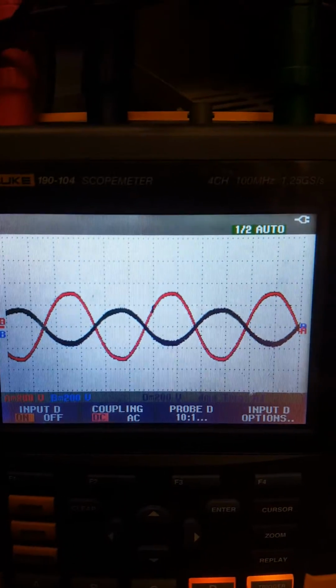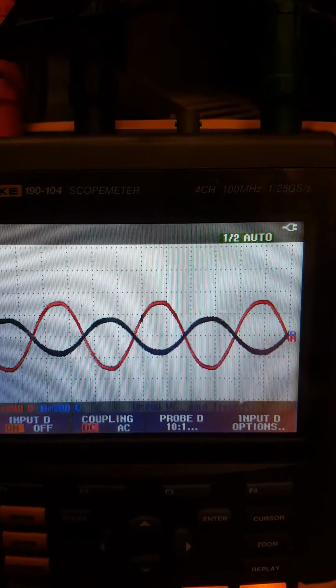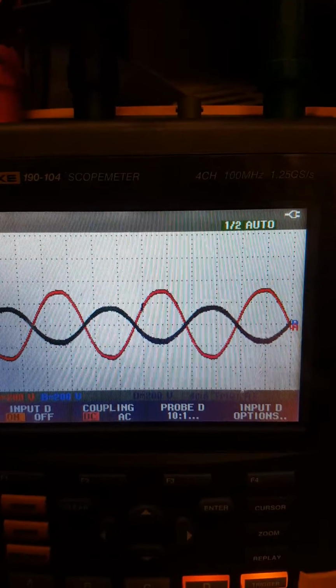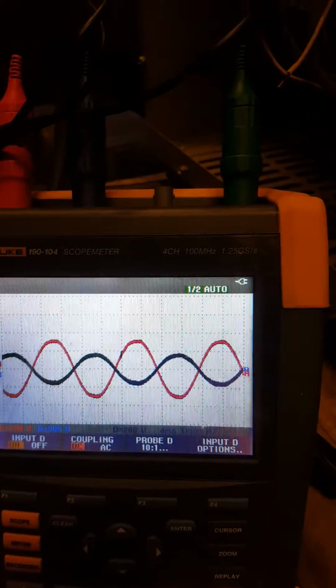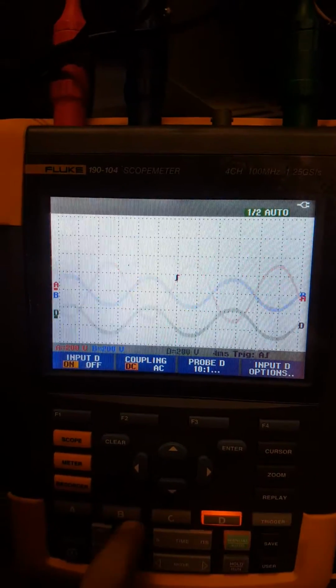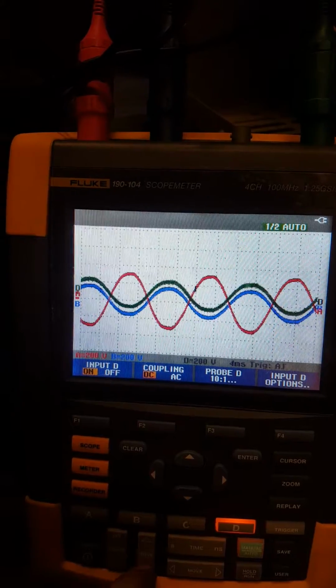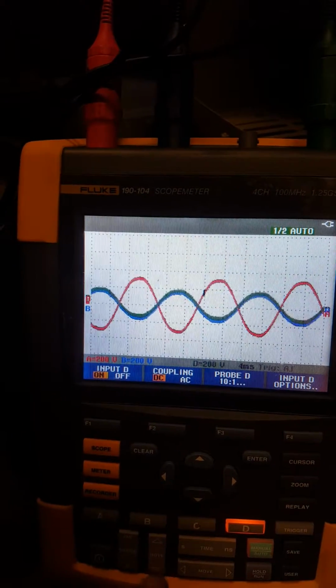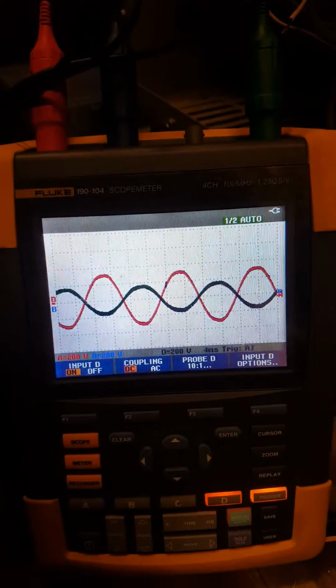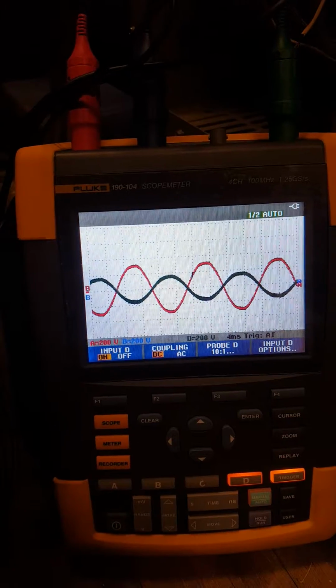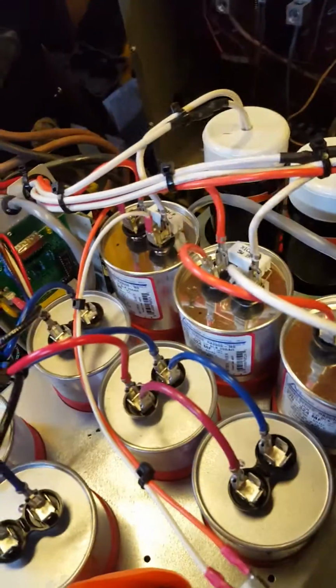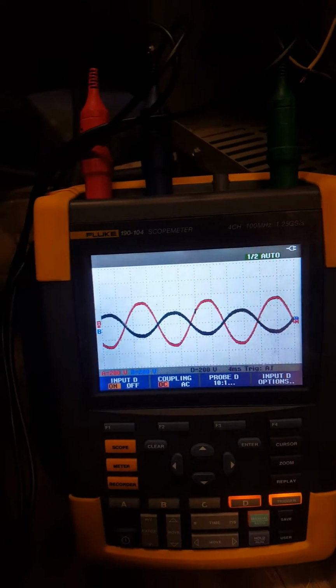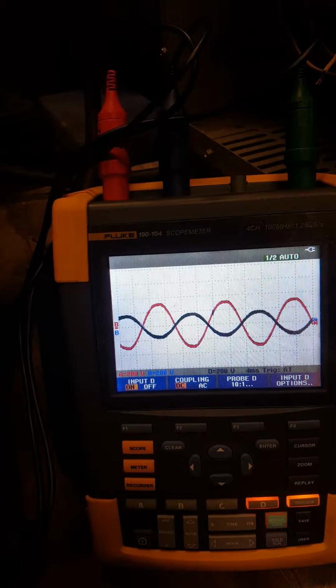So the red probe is the incoming 240 single phase, and we have two traces on top of each other that are 180 degrees out of phase. Those are your other two legs, which are referenced to that generated phase. I'm not sure why we have a trace there at all. I assume it's got something to do with these caps. I'm not sure how all this works, but yeah, we got something there, and it's 180 degrees out of phase. It's probably just a phantom voltage. If we were to put a load on it on the single phase right now, that would probably go away.